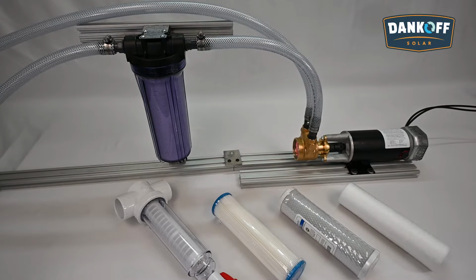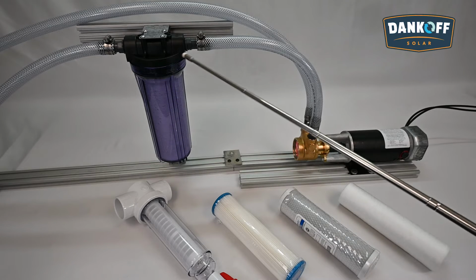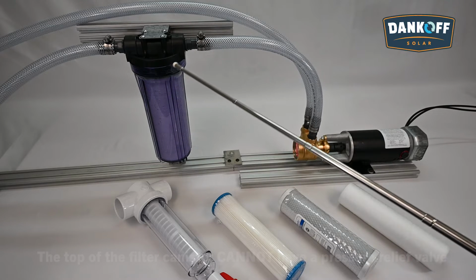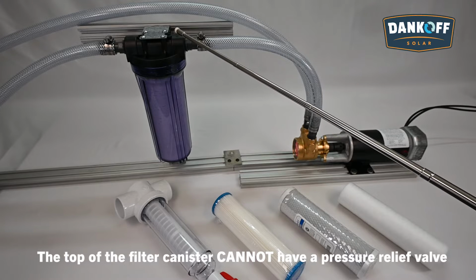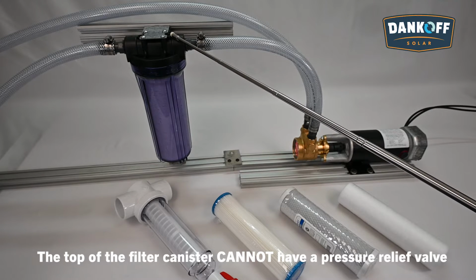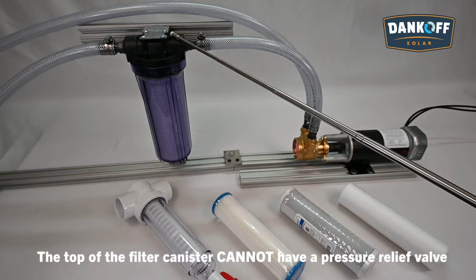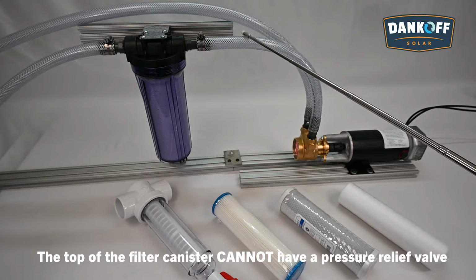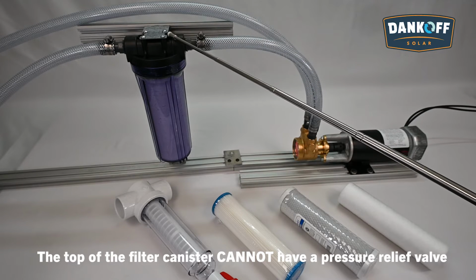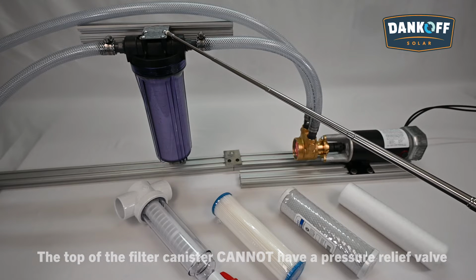If you have just installed a new filter canister and the pump won't draw or cavitates, verify that the top of the filter canister does not have a pressure relief valve in the areas shown here. Third-party filter canisters often have pressure relief valves that are not intended to be installed on the suction side of a pump and will not work correctly.